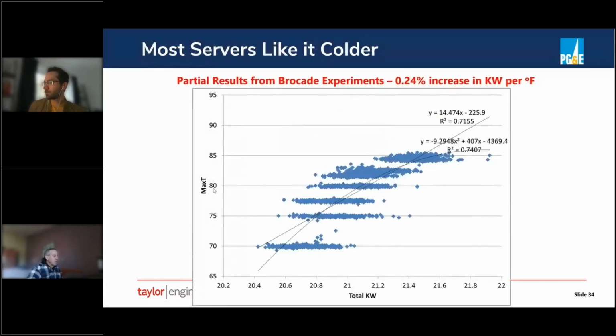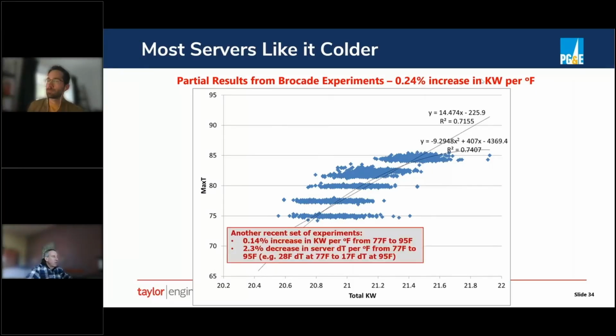Now, there is a trade-off when you operate a computer at a higher temperature. It uses more power, and that's because the servers all have little fans on them to keep them cool, and those fans speed up as the temperature introduced to the server goes up. And this was some experiments we did many years ago at a data center where we characterized that relationship between the temperature and the power. We found on average a 0.24% increase in the power consumption for every degree you raise the temperature. We also found that every degree you raise the temperature, we could save more than this amount of power in our mechanical system. So it was always worthwhile on an energy basis.